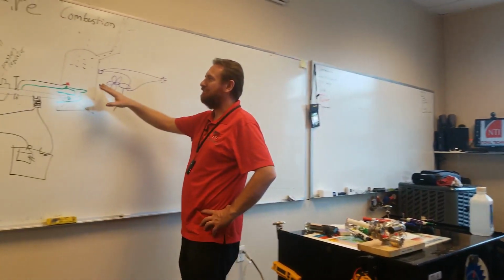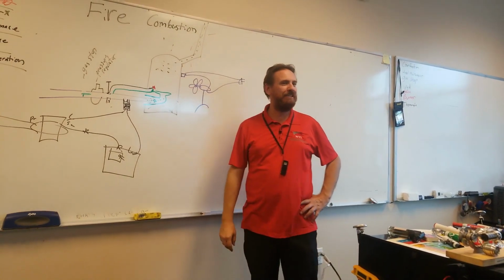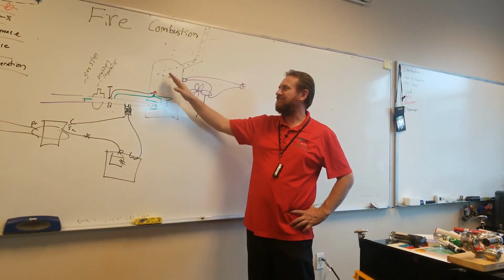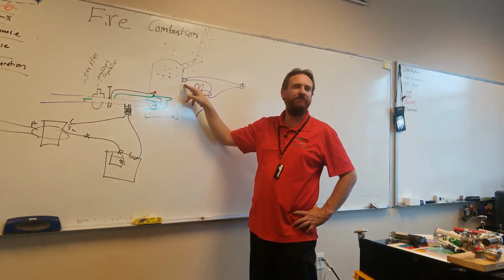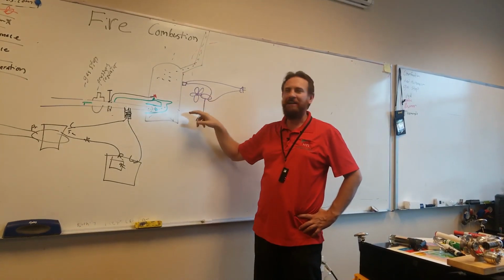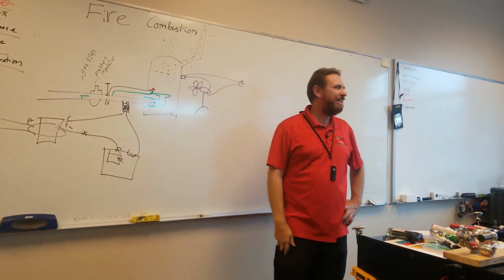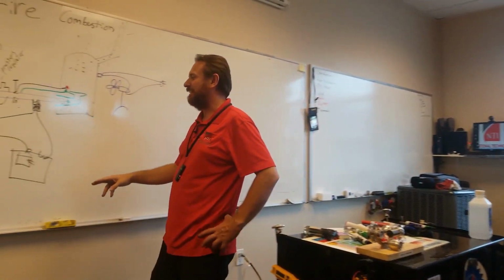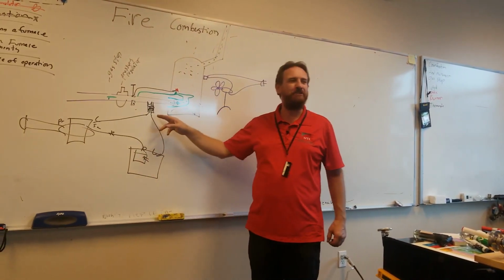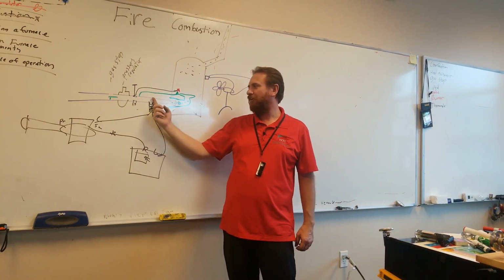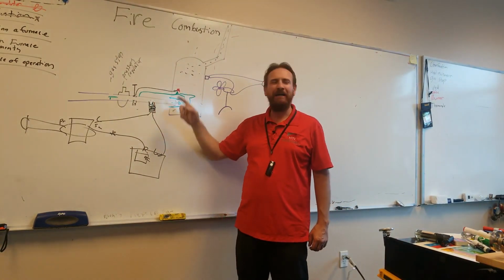The heat exchanger is going to heat up. It doesn't heat up right away, but it's going to take a little bit. It's going to heat up. Once the heat exchanger heats up, this switch is going to close, send power to my fan motor. My fan's going to move air through it, and I want to heat the house. When the house heats up, the thermostat satisfies, breaks R and W, kills my electromagnet. Spring causes that to close, shuts off the main gas, but the pilot light stays on.